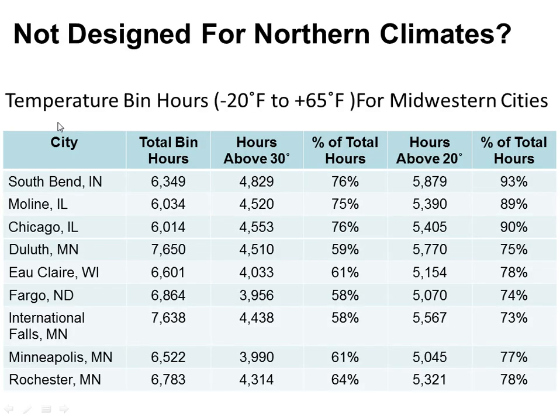So next slide here. Addressing the cold climate scenario, here you'll see the third line down is Chicago, Illinois, representing how many operating hours we have here. This chart is what we call bin hours. Bin hours are basically every hour of the year. So there's something like 8,760 hours in the year. And if you look at Chicago, of those 8,700 hours, 6,000 of them are below 65 degrees outdoor temperature.